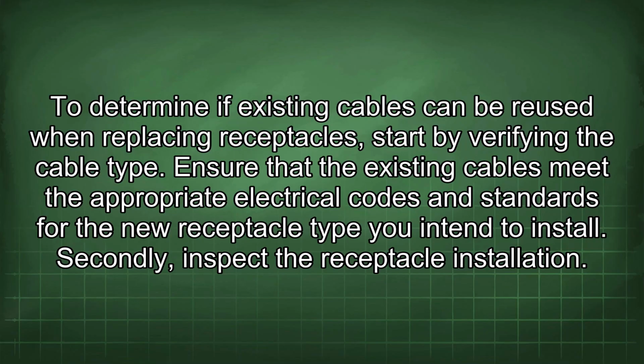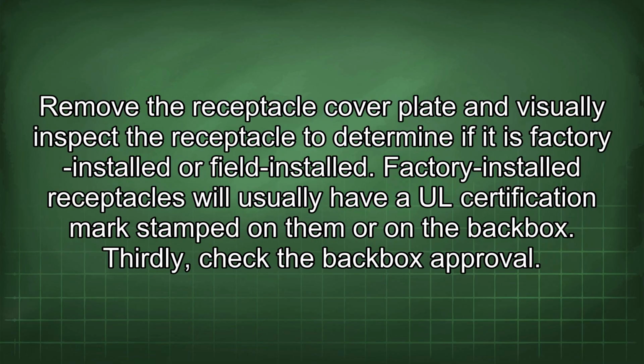To determine if existing cables can be reused when replacing receptacles, start by verifying the cable type. Ensure that the existing cables meet the appropriate electrical codes and standards for the new receptacle type you intend to install. Secondly, inspect the receptacle installation. Remove the receptacle cover plate and visually inspect the receptacle to determine if it is factory installed or field installed. Factory installed receptacles will usually have a UL certification mark stamped on them or on the backbox.